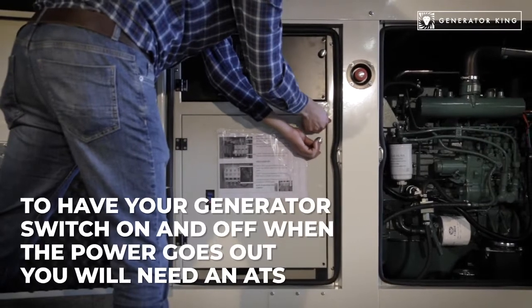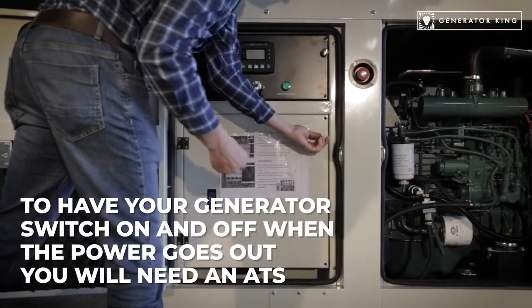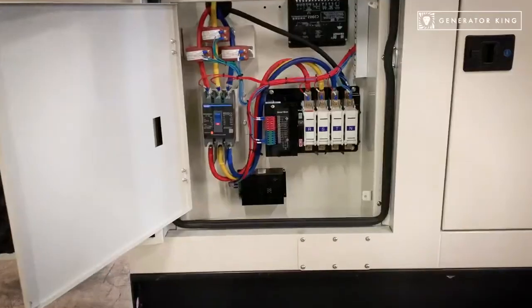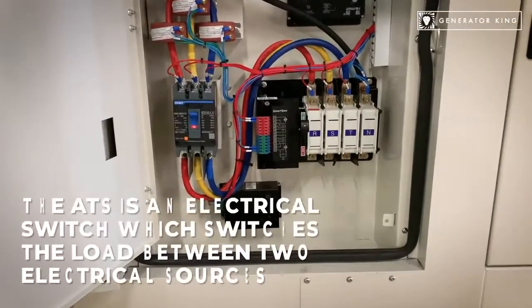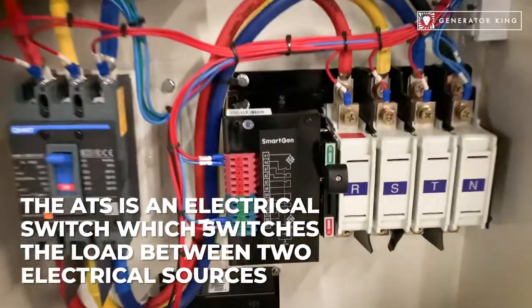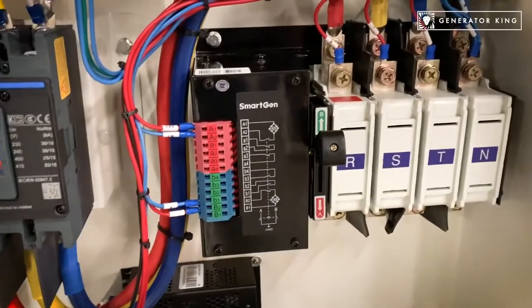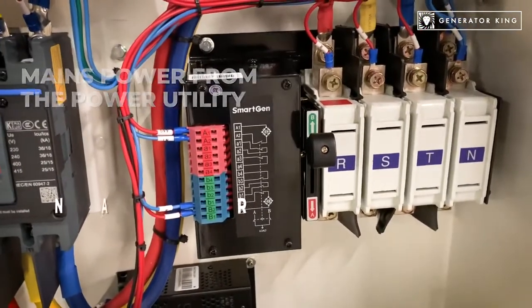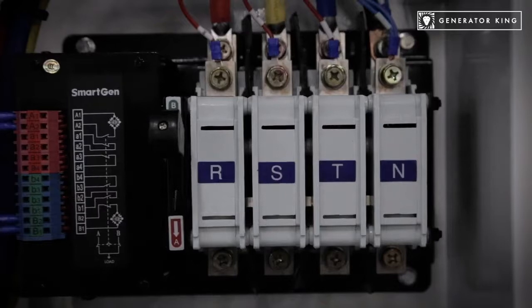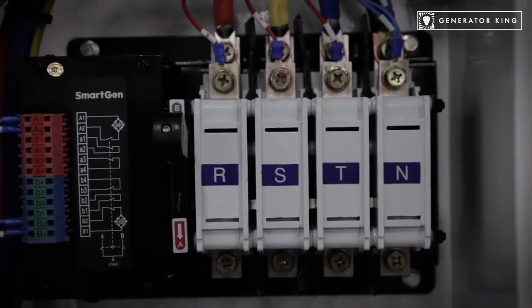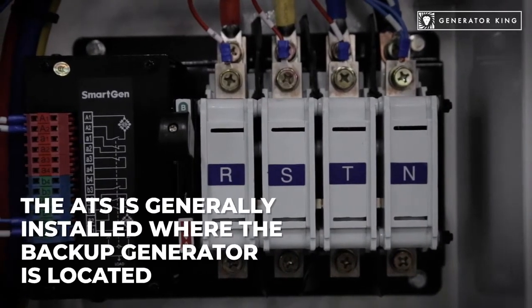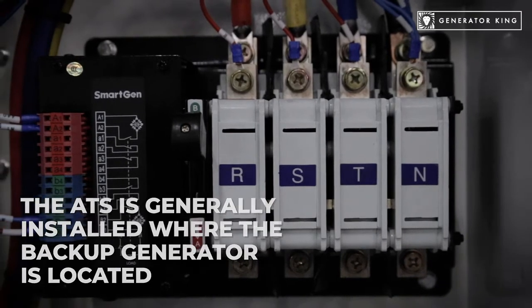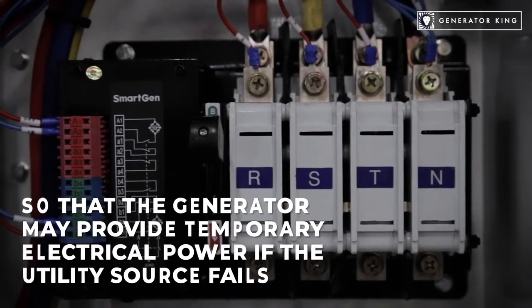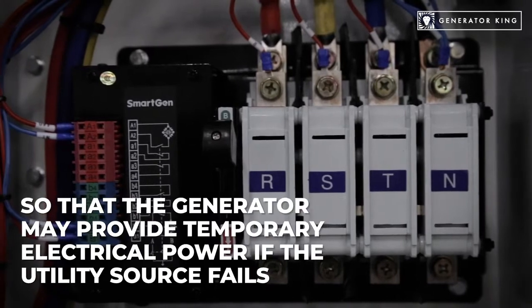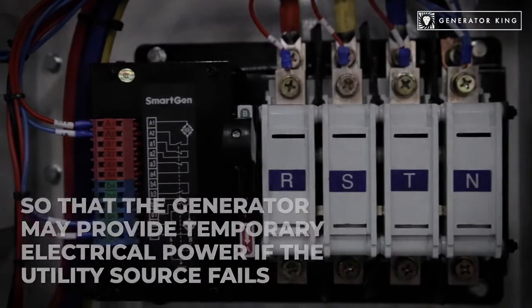If you need your generator to switch on and off by itself when an outage occurs, you will need it fitted with an automatic transfer switch. The automatic transfer switch is an electrical switch that switches a load between two sources, mains power from the power utility and generator power. The generator ATS, or automatic transfer switch, is often installed where a backup generator is located, so that the generator may provide temporary electrical power if the utility source fails.